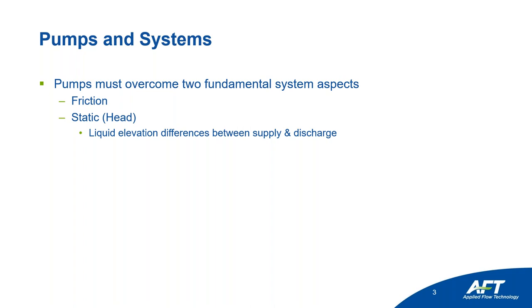The key thing about the static head is that it will not change as the flow rate changes through your system. However, the frictional components of your system will change as your flow rate changes. So your frictional resistance is variable, while your static resistance is static, it's the same.